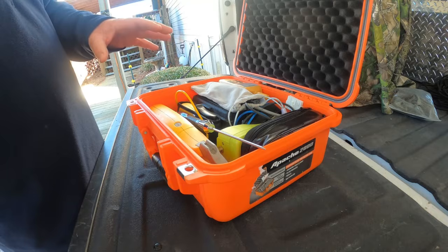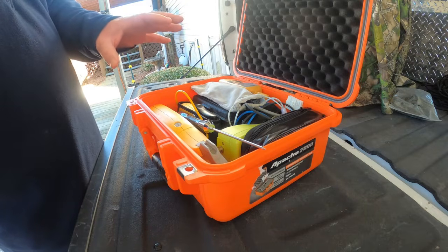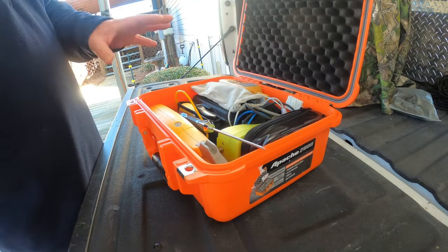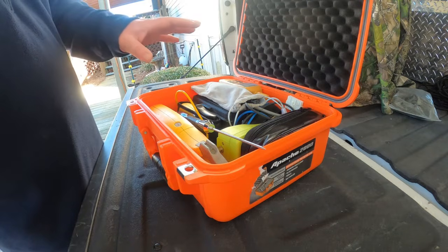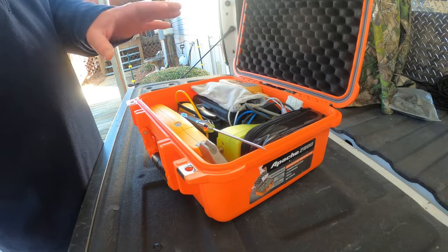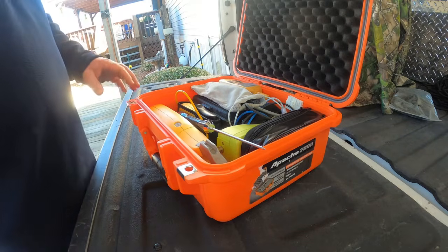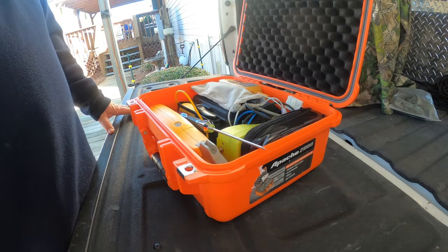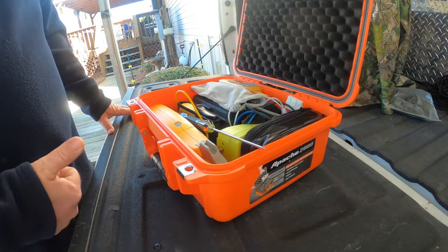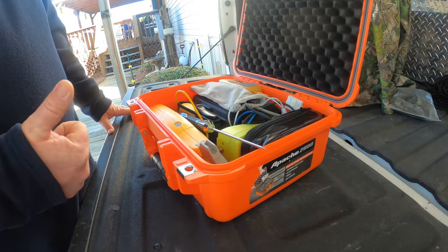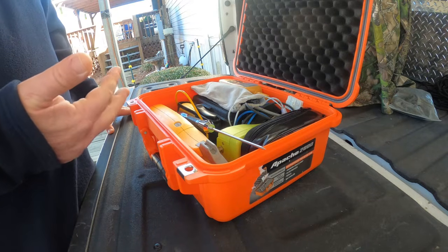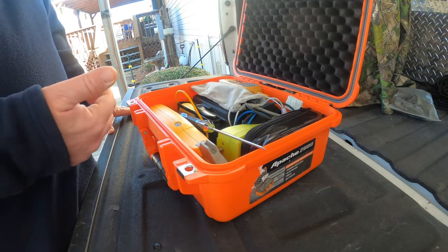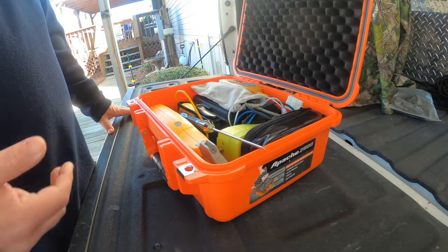X13 motors just require a 24 volt signal. It closes a relay internal to it, it comes on and runs at the requested speed depending on what tap you're plugged to on your low voltage side. If you get to it and it's not running, nothing at all, the motor's not hot, nothing's happening, you want to confirm that you've got your high voltage, and you want to confirm that whichever speed tap you're calling for is getting the 24 volt call to close the relay internal to the motor to ask it to run in that particular speed.